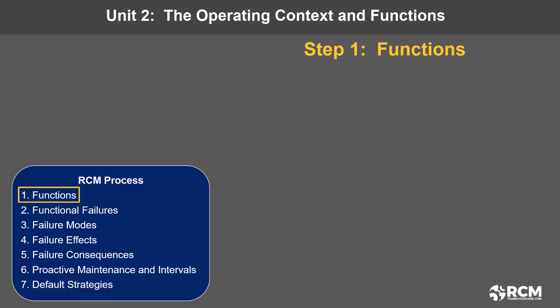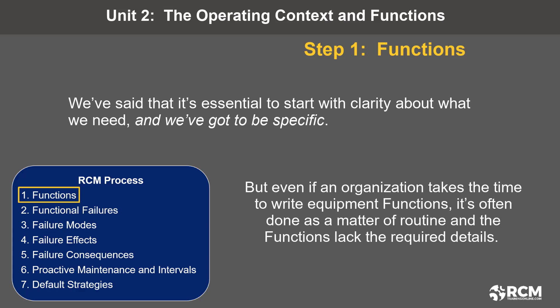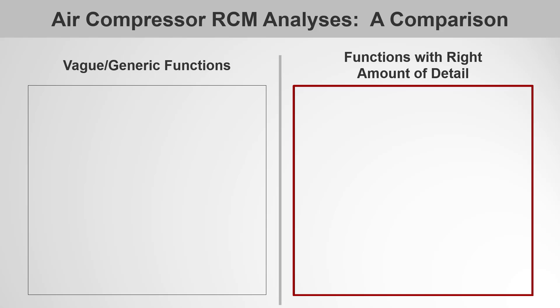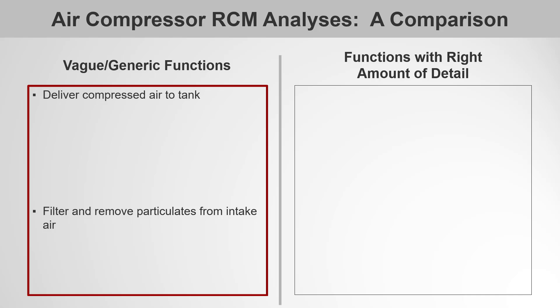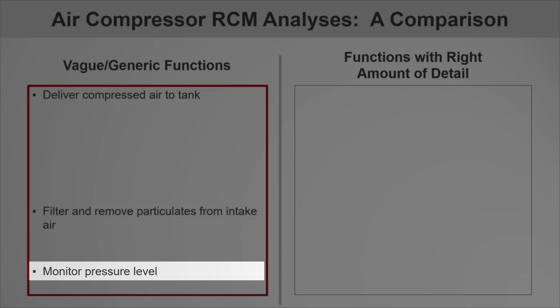It's essential to start with clarity about what we need, and we've got to be specific. But even if an organization takes the time to write equipment functions, it's often done as a matter of routine and the functions lack the required details. Let's look at some real-world examples from an air compressor analysis that I facilitated. On the left side: deliver compressed air to tank; filter and remove particulates from intake air; monitor pressure level. These describe just about every air compressor, every intake air filter, and every pressure indicator — they're generic.